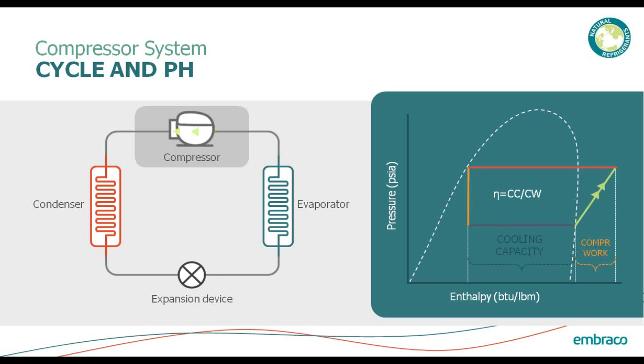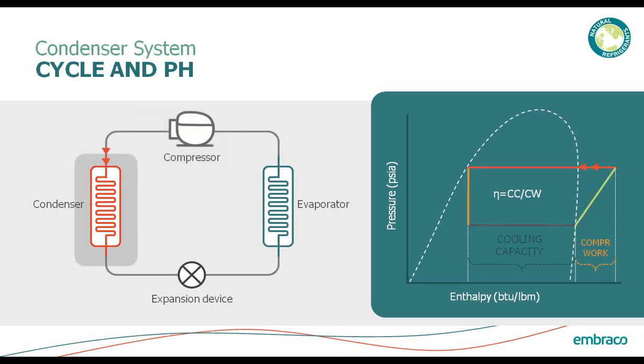Let's look at the compressor side of the system. The compressor is adding work to the system — taking electrical energy and converting it to mechanical work to raise the pressure. This low pressure, relatively low temperature vapor (typically 40 to 90 degrees Fahrenheit) is raised to a very high pressure, high temperature vapor, which could be anywhere from 160 to 200 degrees, by the time it reaches the end.